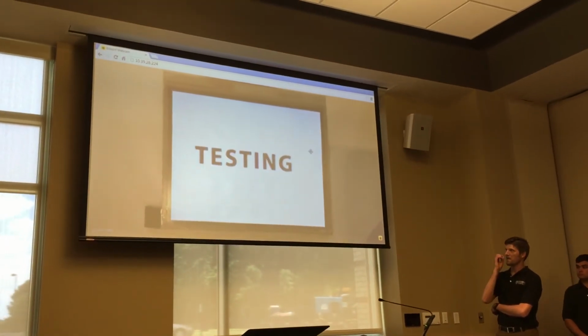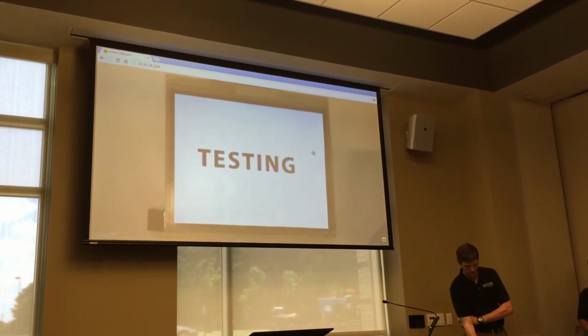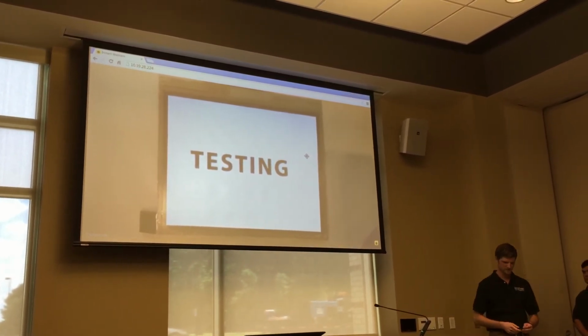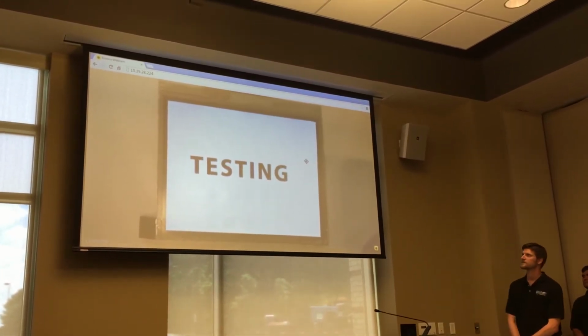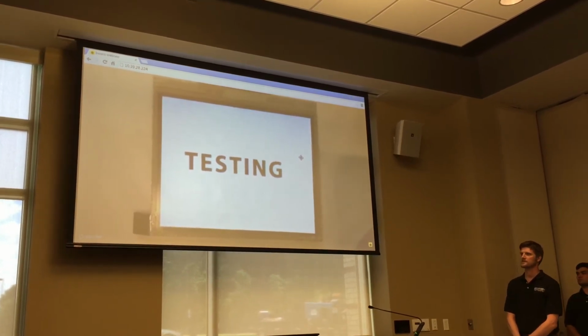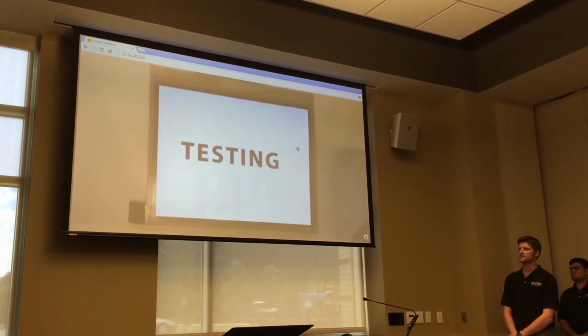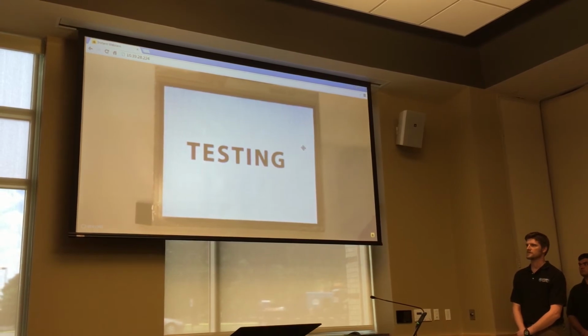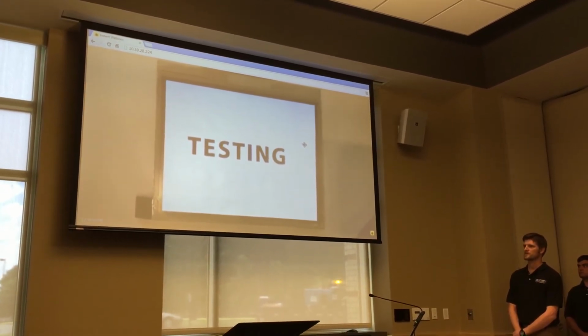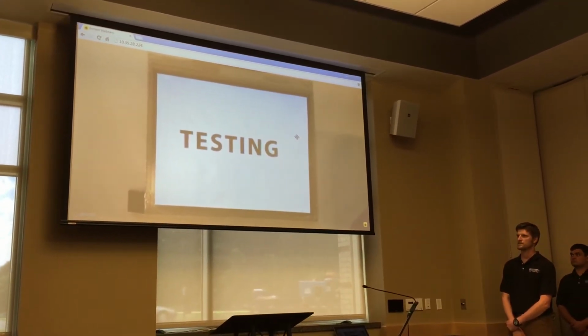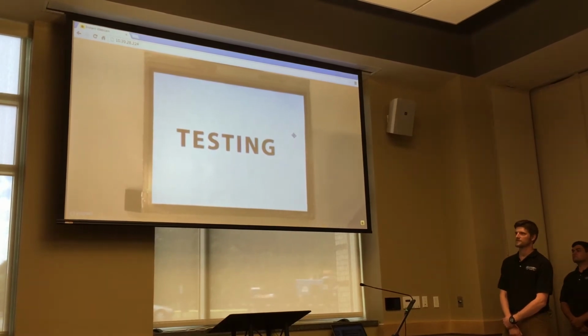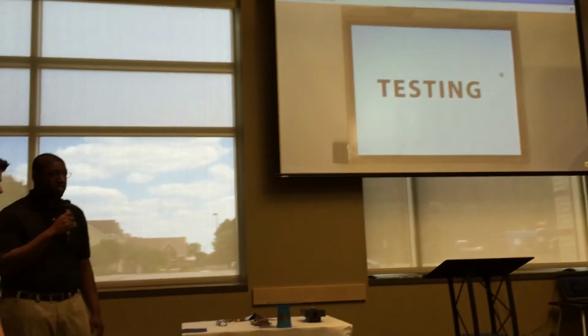Okay, so the device will start by testing for an induced voltage on the coils to make sure there's nothing there that would damage it when it does the impedance test and the leads test. Now it should be applying a DC voltage to the coils to calculate the resistance.